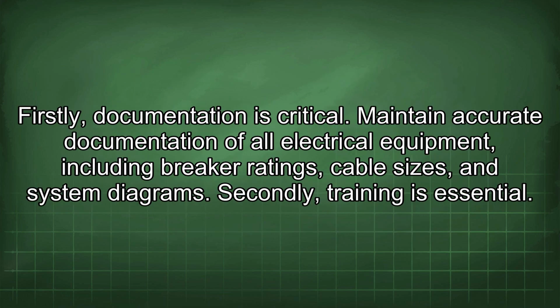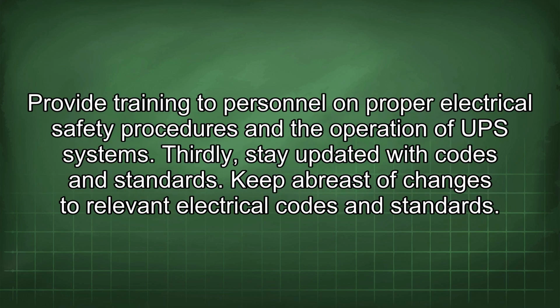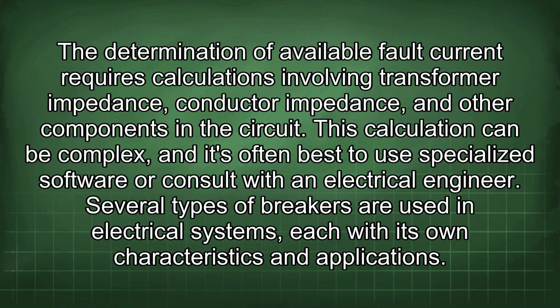Firstly, documentation is critical. Maintain accurate documentation of all electrical equipment, including breaker ratings, cable sizes, and system diagrams. Secondly, training is essential. Provide training to personnel on proper electrical safety procedures and the operation of UPS systems. Thirdly, stay updated with codes and standards. Keep abreast of changes to relevant electrical codes and standards. The determination of available fault current requires calculations involving transformer impedance, conductor impedance, and other components in the circuit. This calculation can be complex, and it's often best to use specialized software or consult with an electrical engineer.